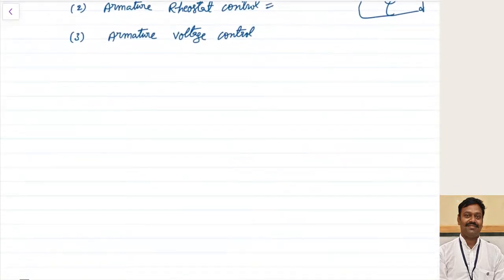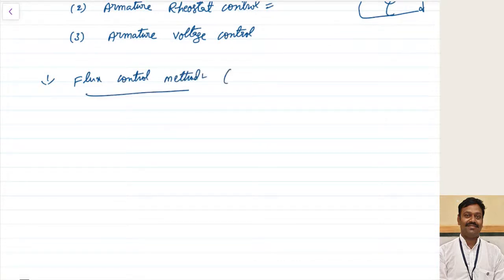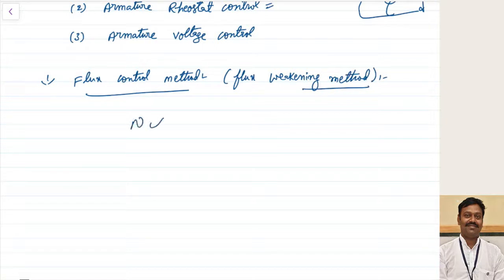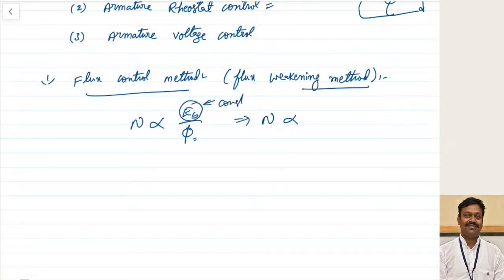The first method is the flux control method, also called the flux weakening method. We know speed is proportional to Eb divided by phi. If we maintain Eb constant and only vary the flux, then speed is inversely proportional to flux. So we can control speed by inversely controlling the flux.